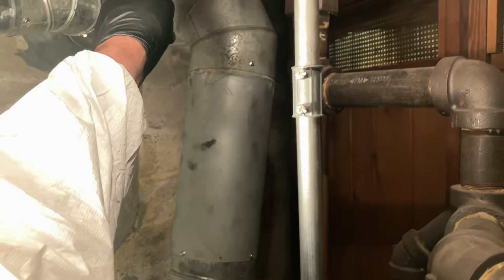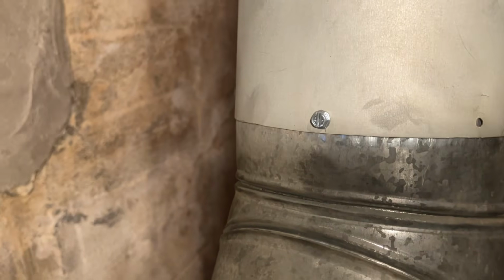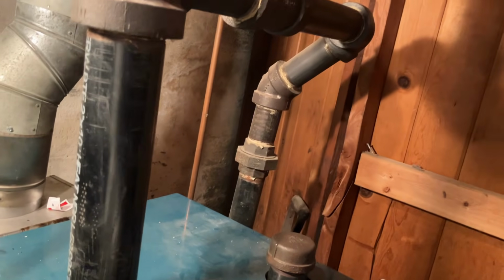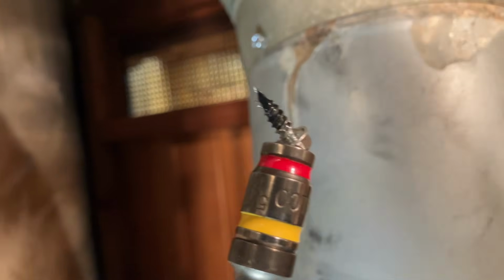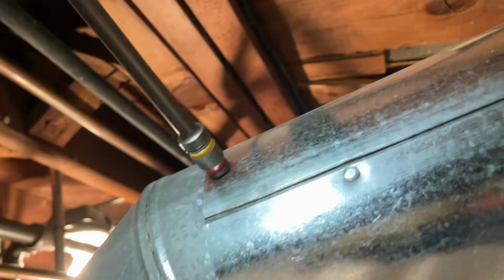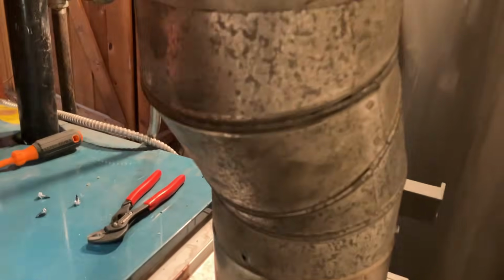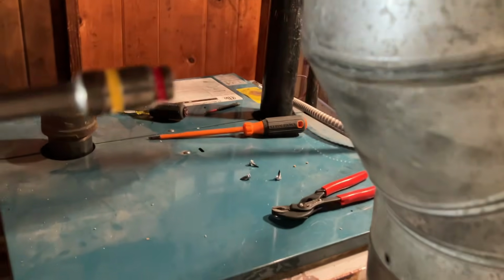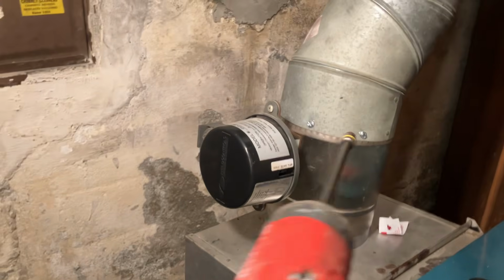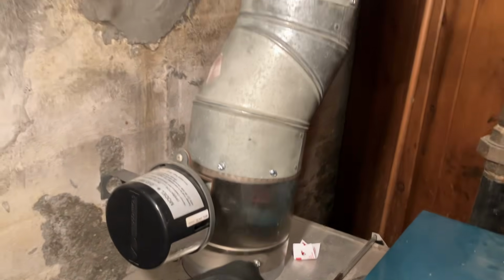Next, I'm going to disconnect the flue piping. Looks like we have a 1/4 inch screw there holding everything in. So let me get a 1/4 inch driver on my impact drill and disconnect the flue. And one of the things you're going to notice when you start taking the screws out, they all got that black film on them. That's the carbon built up on the inside of the flue. So after we do a full cleaning of this system, we are going to recommend that they get their chimney cleaned. It's a Phillips screw, so let me switch that and then we'll pull this whole thing out.